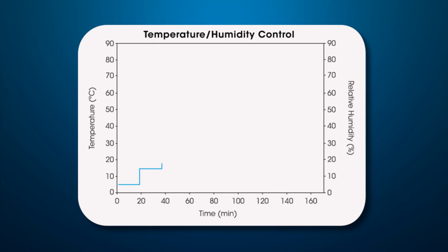The Discovery SA can independently adjust both temperature and humidity in small increments or can continuously ramp each in a linear fashion. This is critical for high resolution measurements.